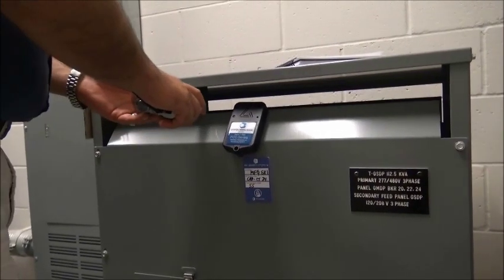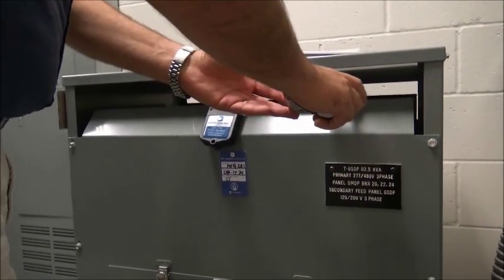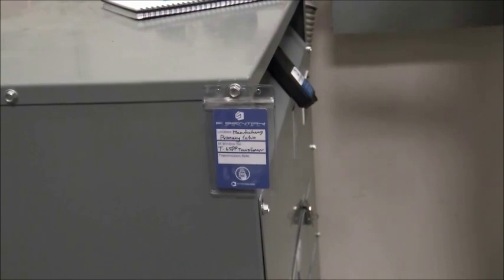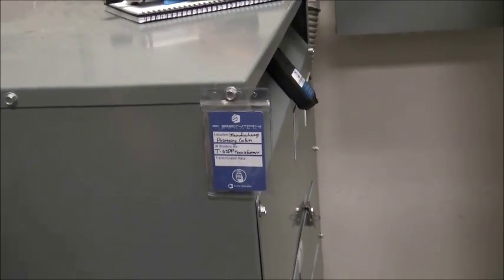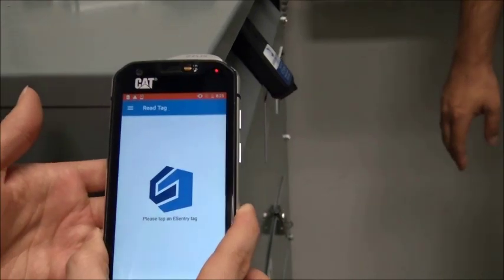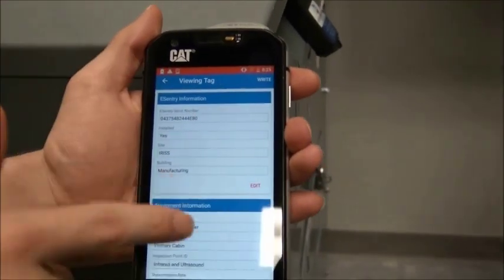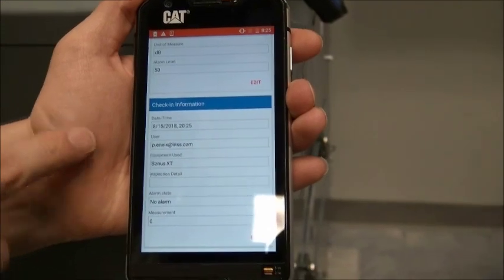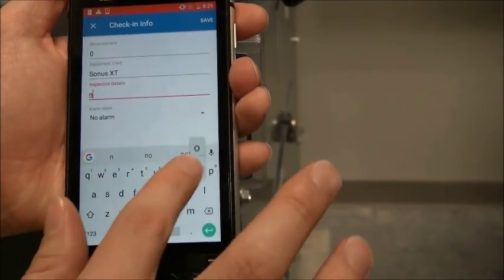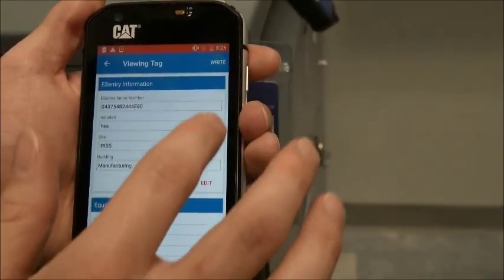Next, our technician moves to a dry type transformer. He scans around the ventilation opening for any ultrasound noise, which would indicate arcing or tracking inside the transformer. Everything seems okay and he records his findings on the eSentry Connect tag. Had he found anything unusual, he could record a sound file using the Sonus XT and the Sonus View app on his smartphone — the same one he's running the NFC app on.